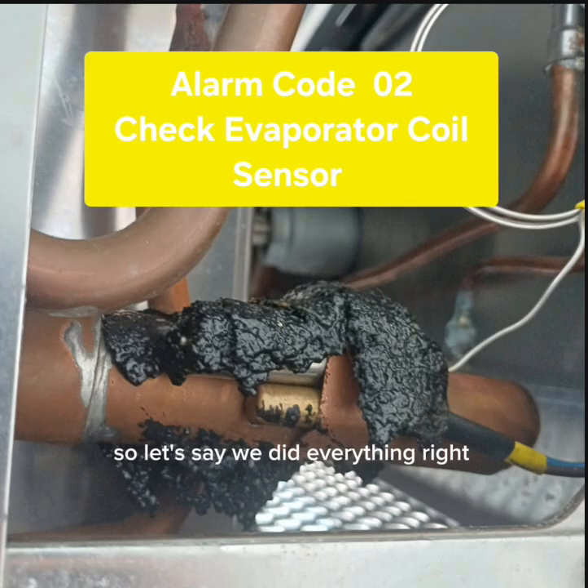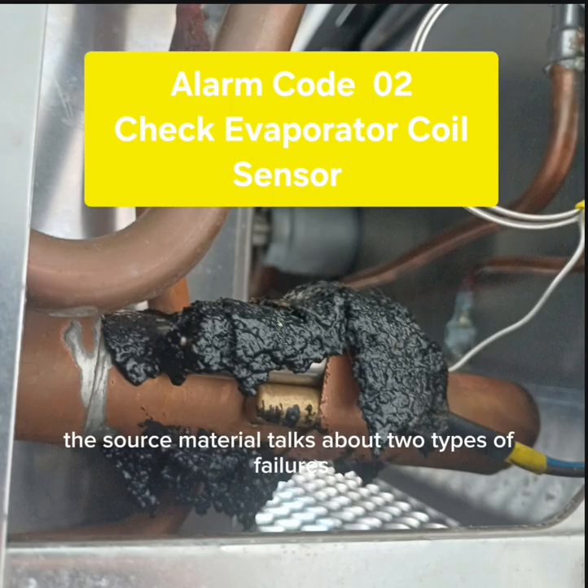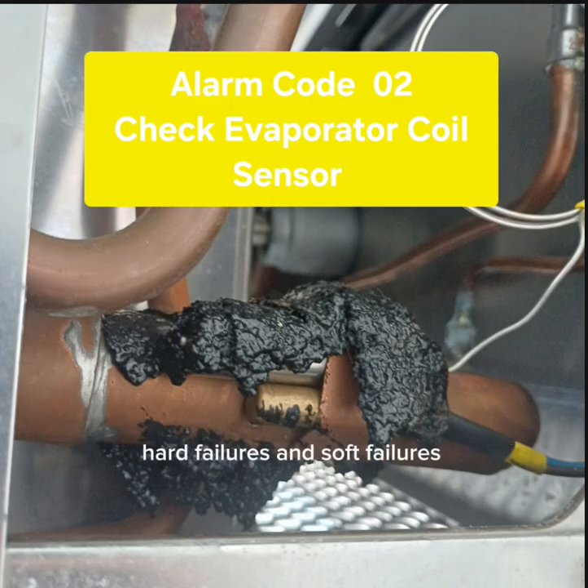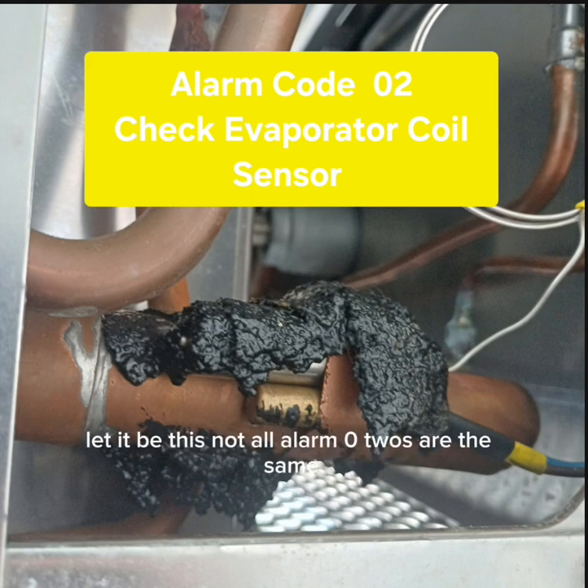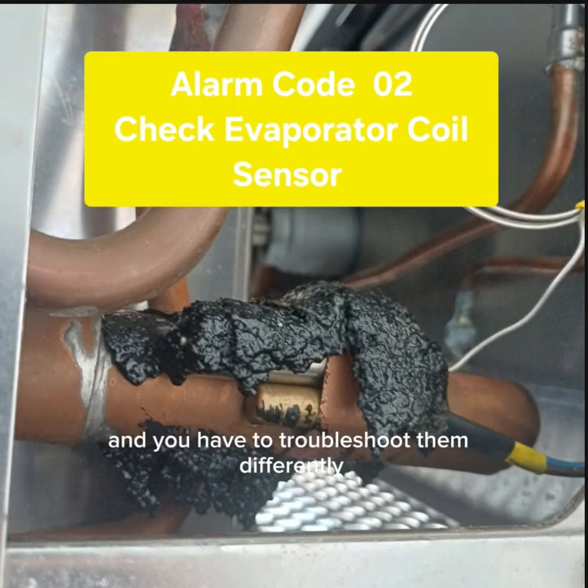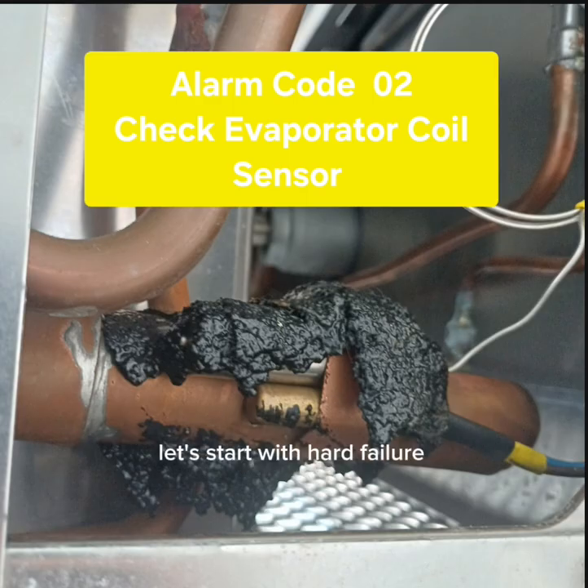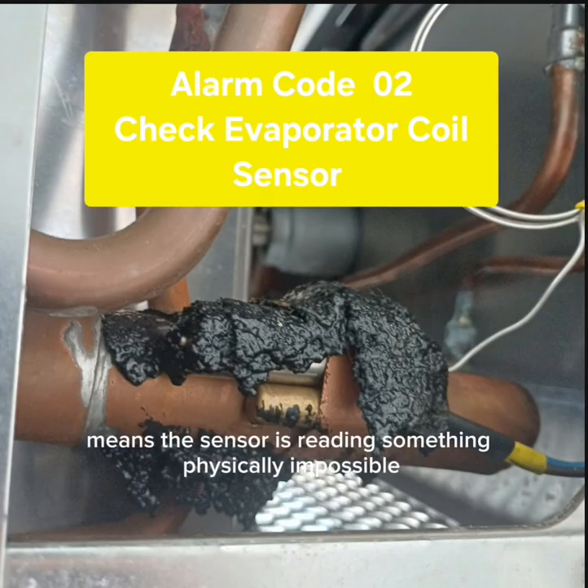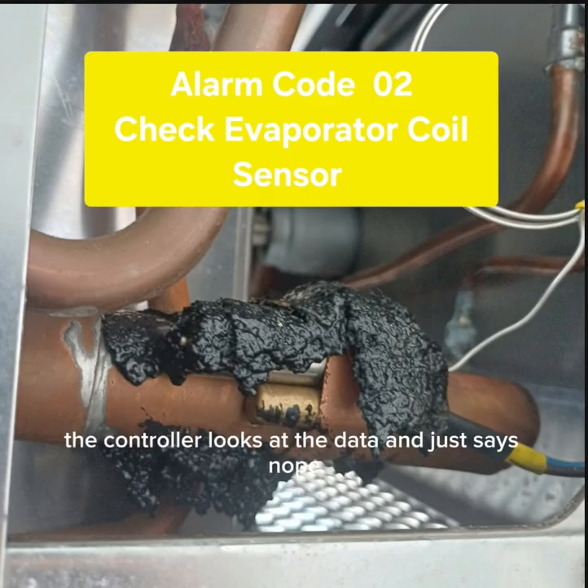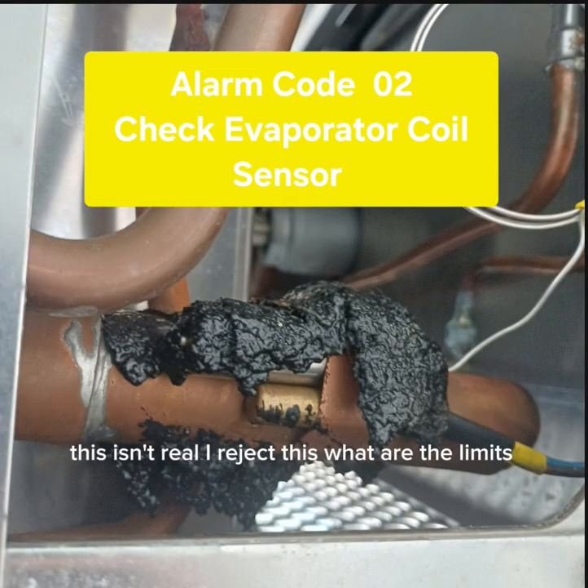Okay, so let's say we did everything right, but the display is flashing alarm 02. The source material talks about two types of failures: hard failures and soft failures. This distinction is critical. If you walk away with one thing today, let it be this. Not all alarm 02s are the same, and you have to troubleshoot them differently. Let's start with hard failure. Sounds dramatic. It is. A hard failure means the sensor is reading something physically impossible. The controller looks at the data and just says, nope, this isn't real. I reject this.